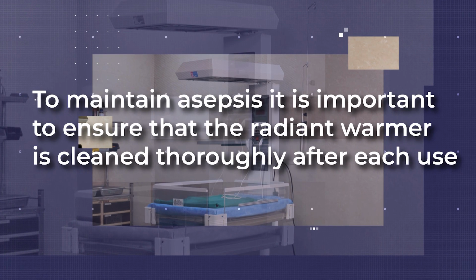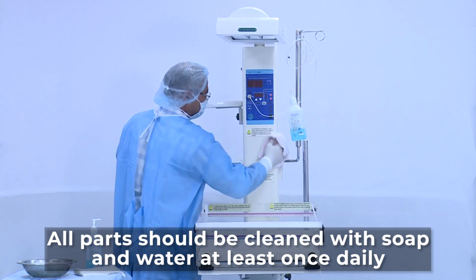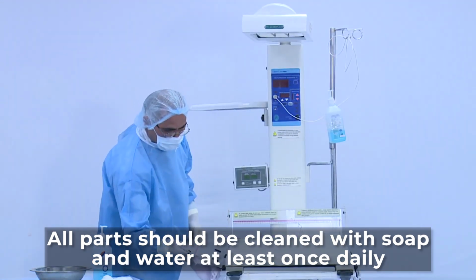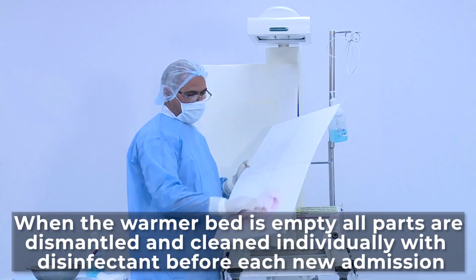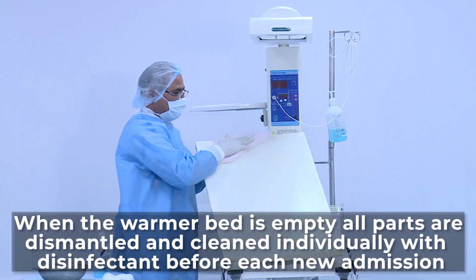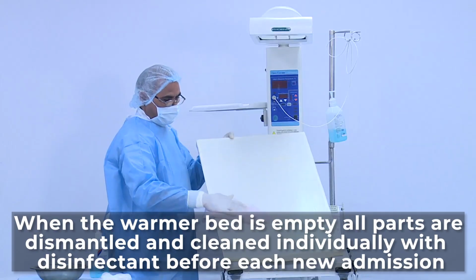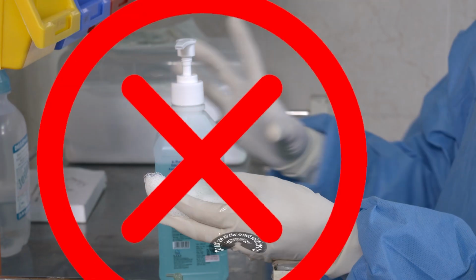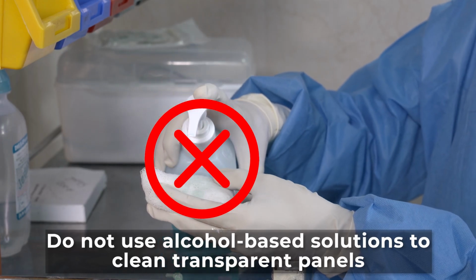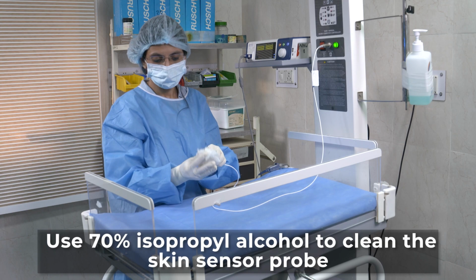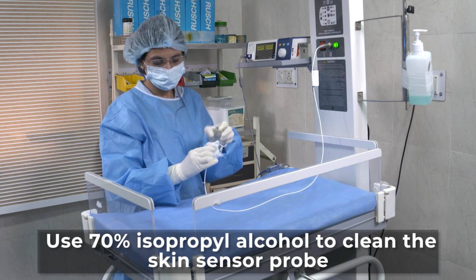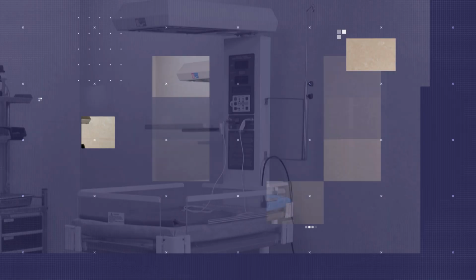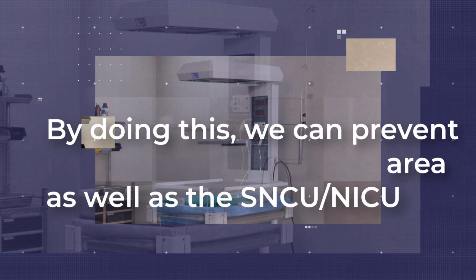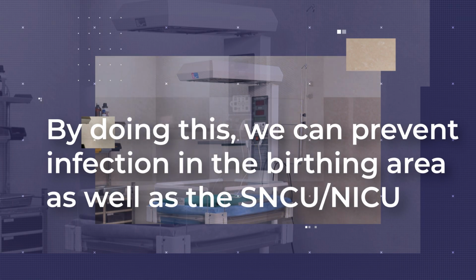To maintain asepsis, it is important to ensure that the radiant warmer is cleaned thoroughly after each use. All parts of the radiant warmer should be cleaned with soap and water at least once daily. When the warmer bed is empty, all parts should be dismantled and cleaned individually with disinfectant before each new admission. Do not use alcohol-based solutions to clean transparent panels. Use 70% isopropyl alcohol to clean the skin sensor probe. By doing this, we can prevent infection in the birthing area as well as in the SNCU or NICU.